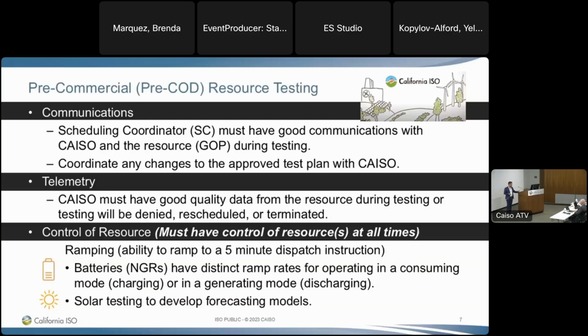So you don't want to go to that. We don't want to go to that because we know opening a breaker on a piece of equipment can cause an issue. But what we're finding is when we call and we try to instruct to take manual action on these resources, it does not seem that the scheduling coordinator or the generator operator has those controls in place to take manual control. Often what we see too, when they go on to regulation, so for batteries, you have the opportunity to get AS certified, providing 2 products, or there's 4 products total, but really 2 products that we have control over, which is regulating units, reg up or reg down.